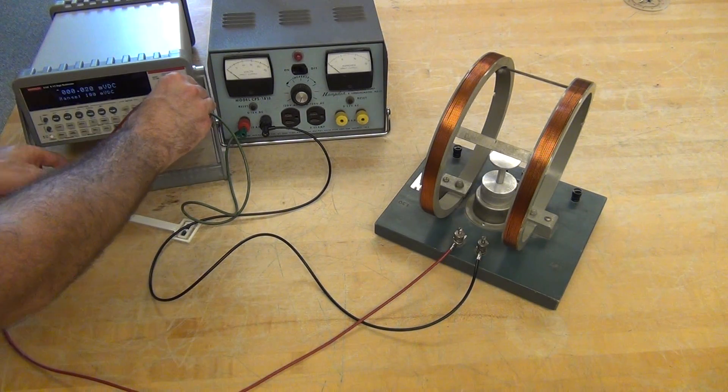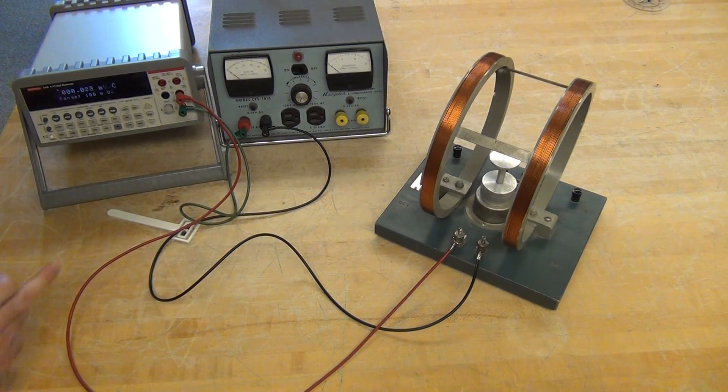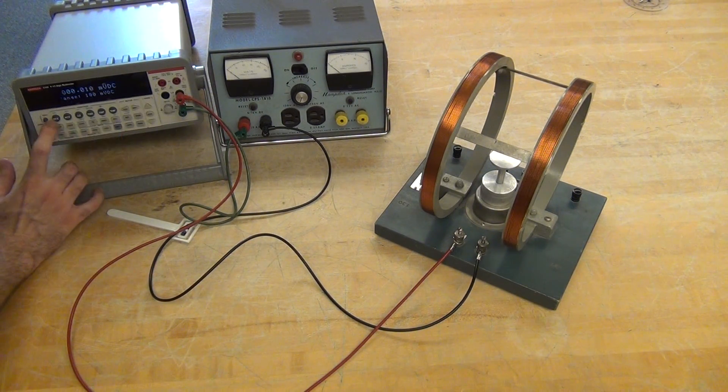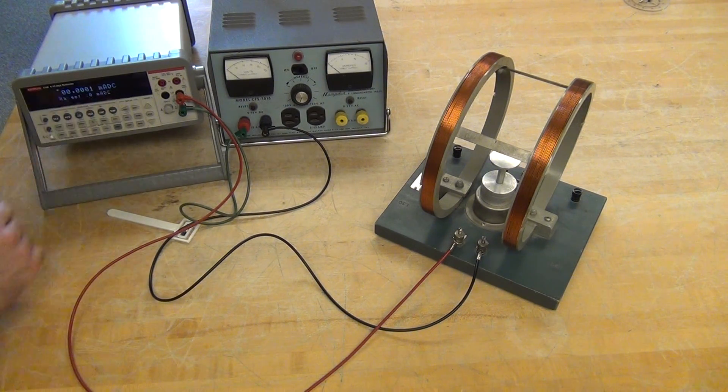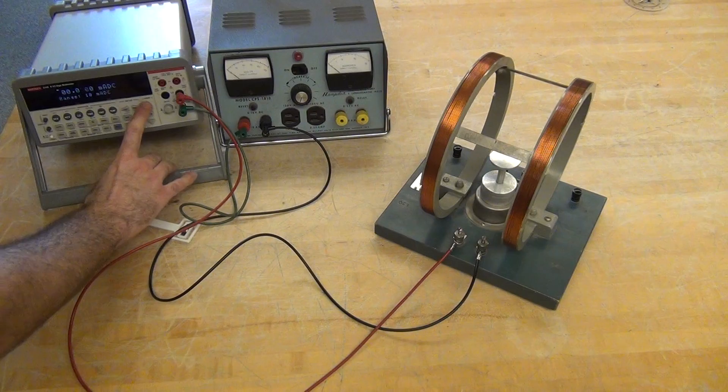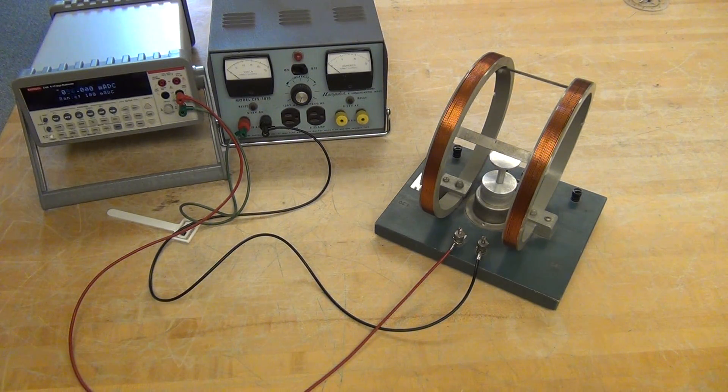Normally the Keithley defaults to measuring voltage, we'll want to switch to measuring current. Use the shift button and now we're in milliamps DC, 10 milliamps maximum range. We'll change that range to 100 milliamps DC.